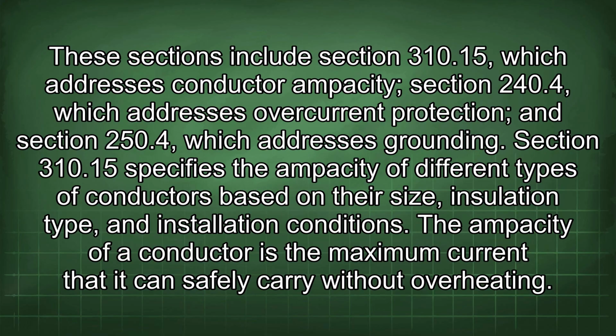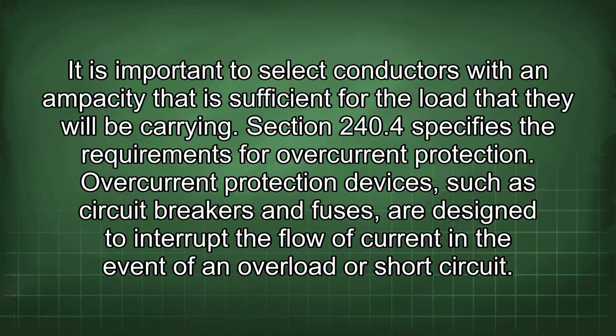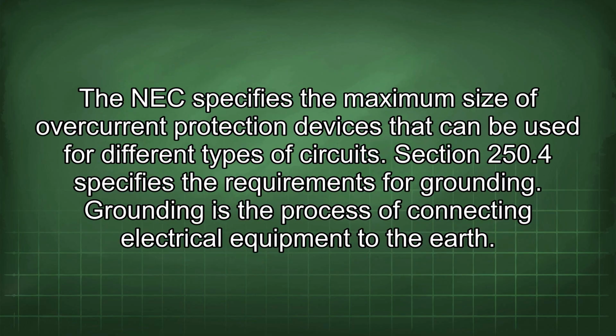Section 310.15 specifies the ampacity of different types of conductors based on their size, insulation type, and installation conditions. The ampacity of a conductor is the maximum current that it can safely carry without overheating. It is important to select conductors with an ampacity that is sufficient for the load that they will be carrying. Section 240.4 specifies the requirements for overcurrent protection. Overcurrent protection devices, such as circuit breakers and fuses, are designed to interrupt the flow of current in the event of an overload or short circuit. The NEC specifies the maximum size of overcurrent protection devices that can be used for different types of circuits.